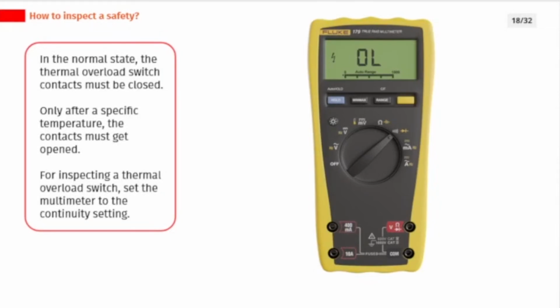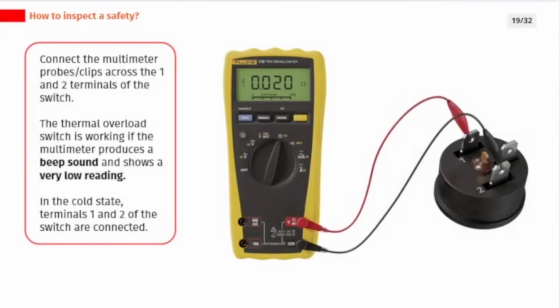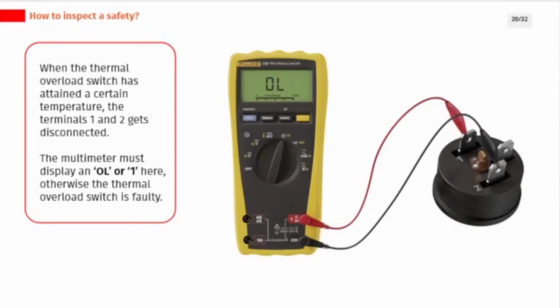For inspecting a thermal overload switch, set the multimeter to the continuity setting. Connect the multimeter probes or clips across the 1 and 2 terminals of the switch. The thermal overload switch is working if the multimeter produces a beep sound and shows a very low reading. In the cold state, terminals 1 and 2 of the switch are connected. When the thermal overload switch has attained a certain temperature, the terminals 1 and 2 get disconnected. The multimeter must display an OL or 1 here, otherwise the thermal overload switch is faulty.